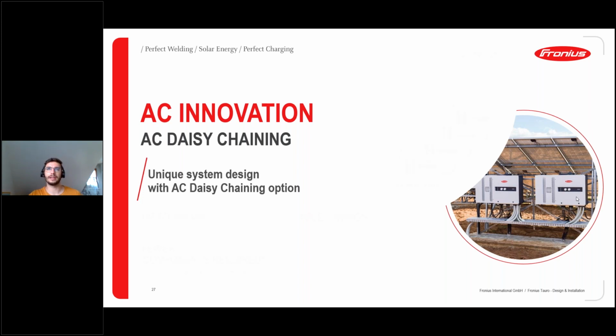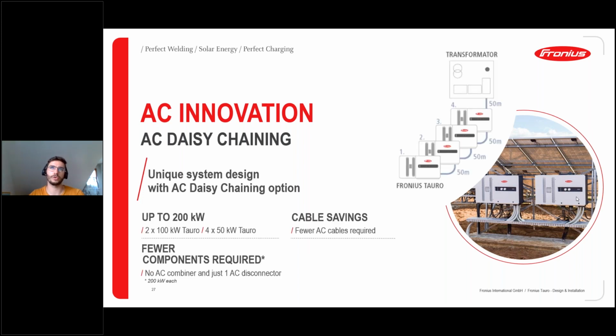Let me explain in a little bit more detail what this means. Of course, we have some limitations here, and the limitation is 200 kilowatt can be maximally interconnected. So this can mean 2 times 100 kW devices, or 4 times 50 kW devices, which can be seen in the schematic here. So we really go from one device to the next one, to the next and the next, and only from the last one we then connect to the main distribution frame.